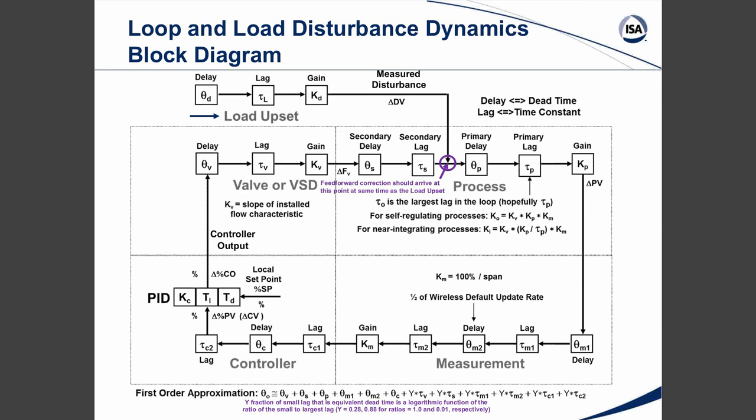And I have to do more recollection of what it was. But again, it comes down to understanding and testing what's being done. What we really needed to do is to make sure that we never generated a negative feed forward signal coming into the feed forward summer. And that was a surprise because we never saw any documentation where we needed to prevent a negative feed forward signal coming in. Because the scale was set 0 to 100,000 pounds per hour, we thought we were all protected anyway.